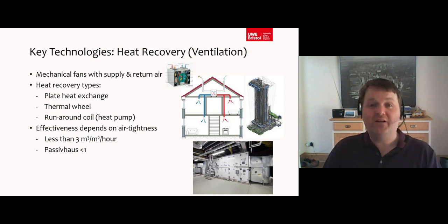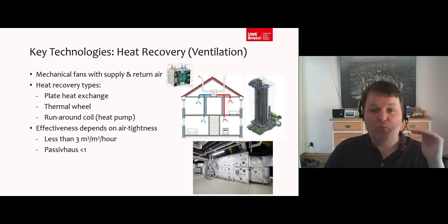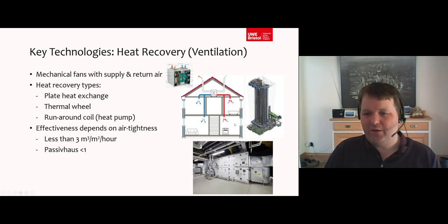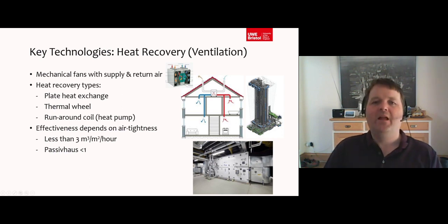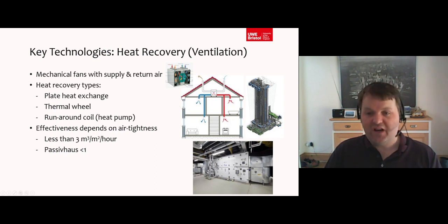And indeed, the passive house standard is to get the air tightness of your structure below 1 to maximize the efficiency of these MVHR devices, in that it's recovering more energy from the heat and supplying that into the return air, and you're not losing that valuable heat out through leakiness in your building. So that's why air tightness testing is very important when it comes to making sure these technologies work. Look there, the units: meter cubed of air for every meter square of surface area of the external per hour. That's what that unit means.